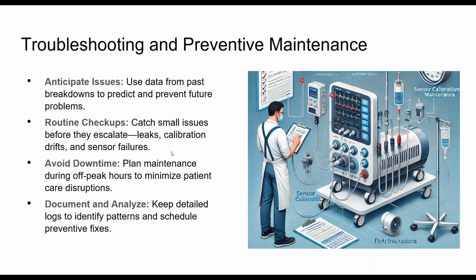Do your routine checkups. It's not good enough. It's never probably been good enough, especially on things like ventilators, to just see them once every 6 months, once every 10,000 or 2,500 hours. It's important to try and catch some of the small issues. If you have a relationship with your RT department, look at things, see how they're looking, see if they're being taken care of, see if there's cracks or whatever. And the routine checks category here too is also about your respiratory therapists, or those people that support the respiratory therapists, the equipment technicians. Those folks should be looking for minor things before they become major.